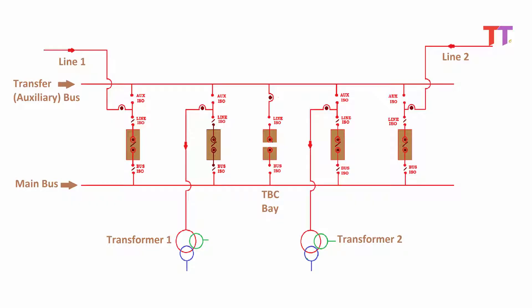Because of this arrangement, the load of any bay can be shifted onto the transfer bus. For example, to shift the load of transformer 1 to the transfer bus: first, close the auxiliary isolator of transformer 1; close both isolators of the TBC bay; charge the TBC breaker; open the main circuit breaker of transformer 1; then open the bus and line isolators of transformer 1. Hence, the load of transformer 1 is shifted to the transfer bus. To take the load back to the main bus, the exact reverse procedure is followed: close bus and line isolators of transformer 1, close the circuit breaker of transformer 1, open the TBC circuit breaker along with both TBC isolators, and finally open the auxiliary isolator of transformer 1. Note: in case of a fault on the main bus, all bays connected to the bus get interrupted.